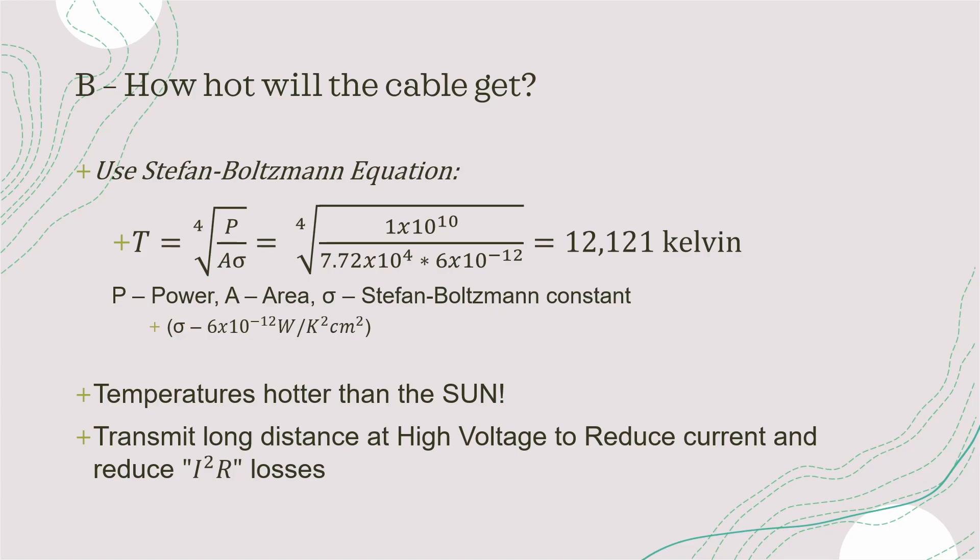You have a lot of losses in the system due to your current and you can reduce the current consumption by increasing the voltage. For long distances you want to transmit your power at 15 kilovolts or maybe 30 kilovolts and that will reduce your current significantly, reducing your I squared R losses.